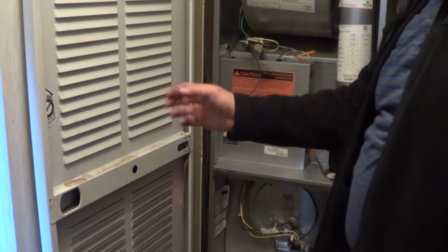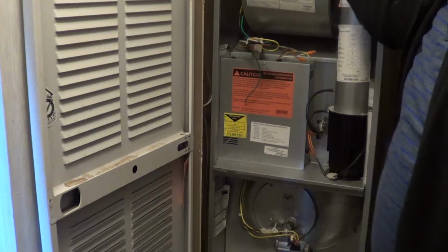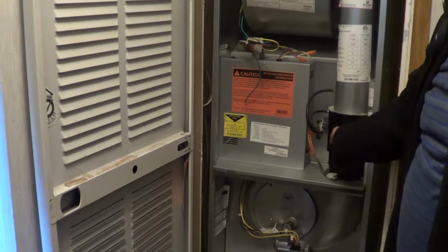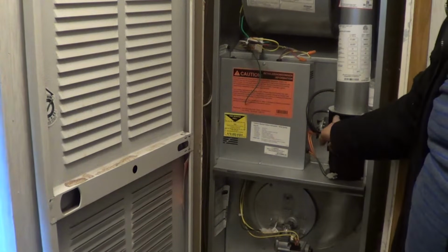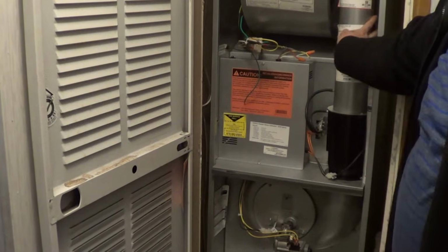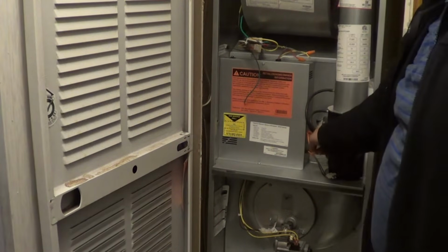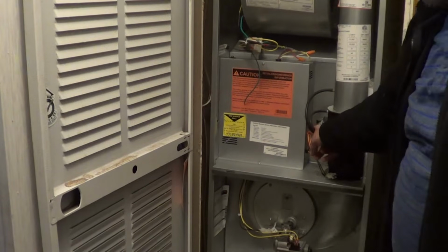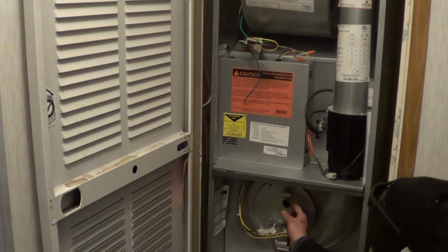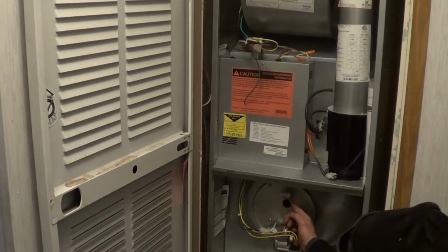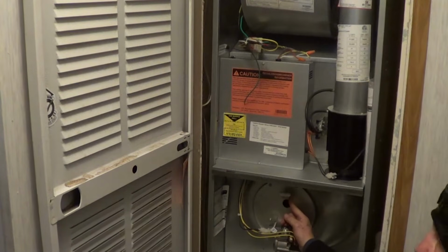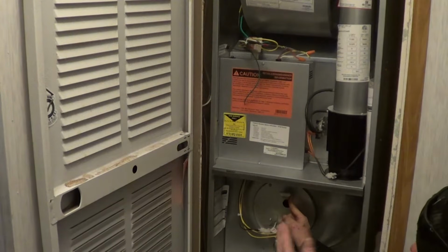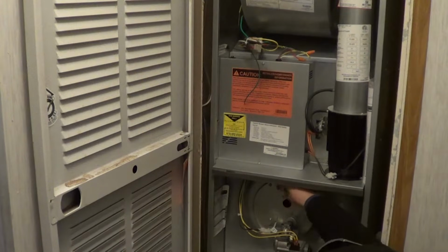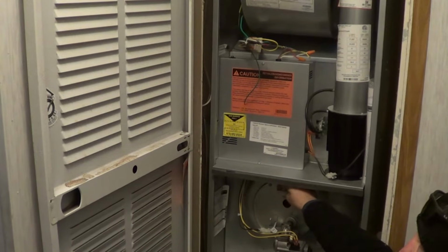Okay, so we've turned the power back on, the thermostat is up. The first step in the sequence of operations on this furnace is that the inducer motor, or the combustion air motor, starts pulling in air from outside on the roof, and then it proves how much air it's getting through this little pressure switch. Then it'll turn on an igniter inside of this hole here. You'll know that it's working correctly because you'll hear a bunch of different clicking sounds. I heard it click on when the thermostat came on, and it clicks on now that the igniter comes on. If we look close, we'll be able to see in there that it's starting to glow.